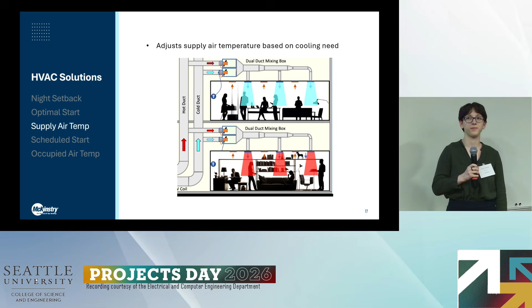Then we tested supply air temperature adjustment. This is the temperature of the cold deck and hot deck air that is mixed to cool and heat the building. One thing to note here is that this is the only strategy that would apply to the zones that hold art because of the strict temperature and humidity requirements in those zones.